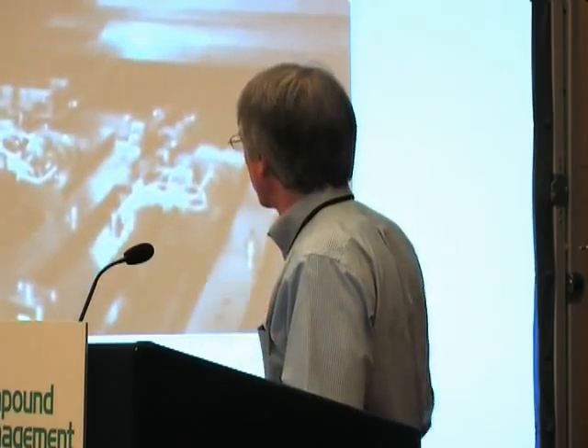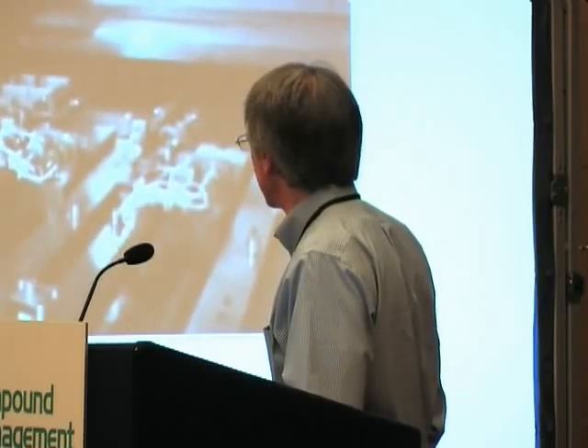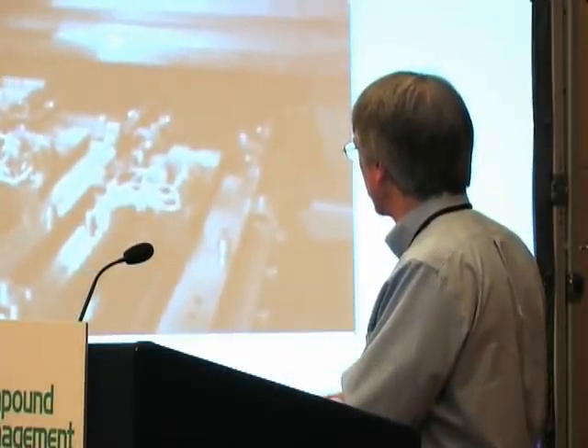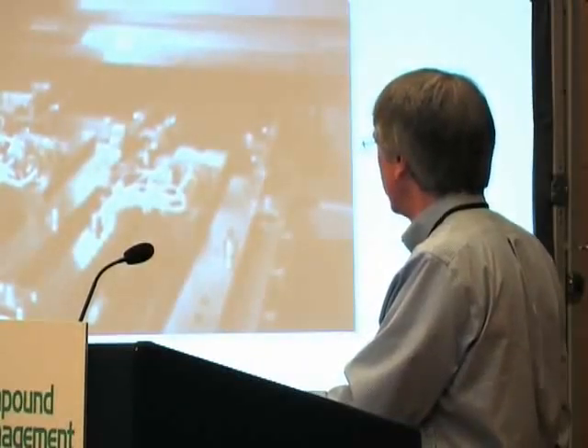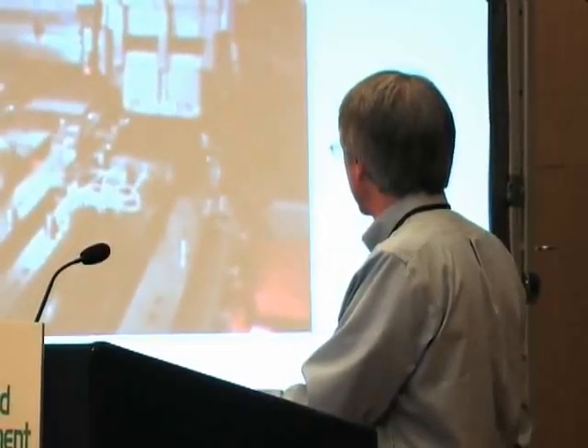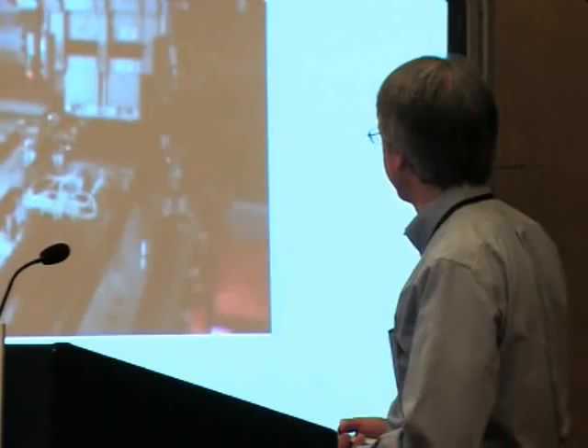And what you see now is it's picking up more compounds from way over there. It's going to do a quick vision check and then bring them over to this side where it'll drop them off. So it's picking up from each of those individual racks on that storage tray as many of the tubes as it can get before it comes over and does a dispense. So here's the dispense action, and then it'll stop.